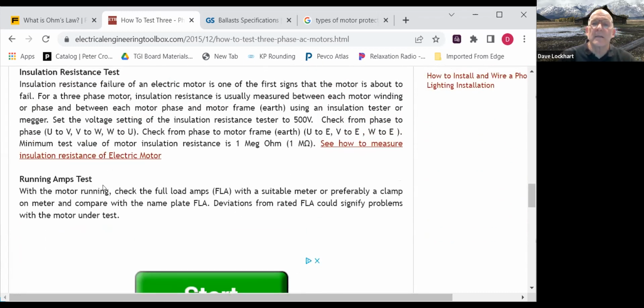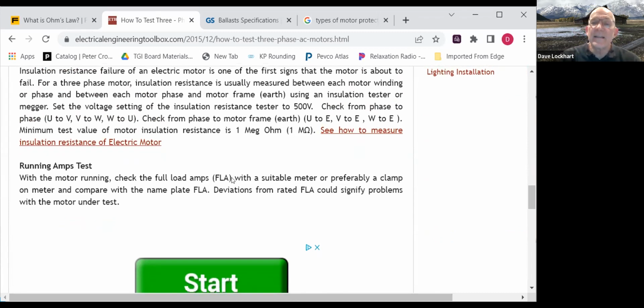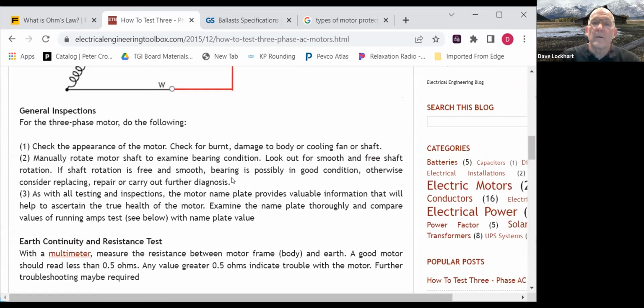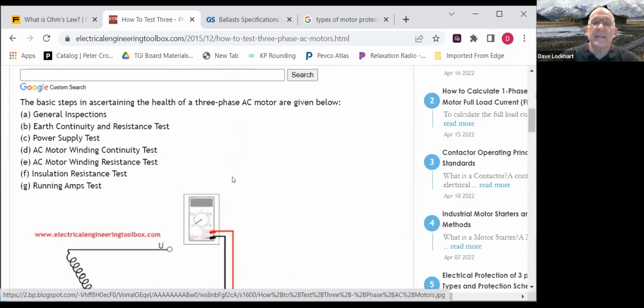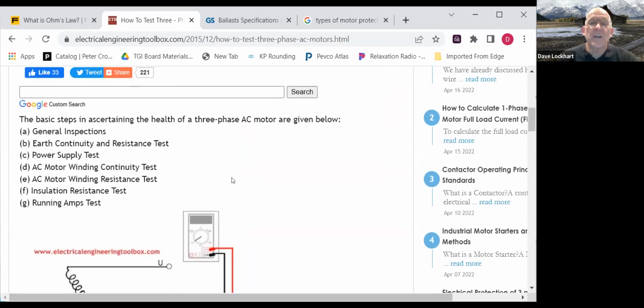Then you've got your running amp test. This is where you use a clamp-on meter and measure the amperage. When that motor is running, you want to make sure your phases are pretty well balanced. They should be balanced if your resistance is good. If they're not, you may have a failing winding in that motor. So that's what we do for motor testing and inspections. You also want to check, when you power it up, that you've got good power coming in. As I talked about, check for phase imbalance, make sure your voltage is good across each of the phases, and make sure your motor is grounded properly. Those are some of the simple tests for checking that a motor is operating properly.